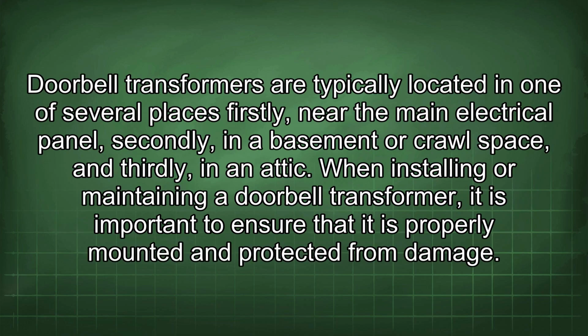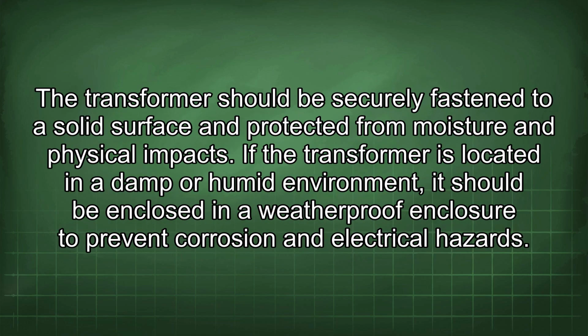Doorbell transformers are typically located in one of several places. Firstly, near the main electrical panel, secondly, in a basement or crawl space, and thirdly, in an attic. When installing or maintaining a doorbell transformer, it is important to ensure that it is properly mounted and protected from damage. The transformer should be securely fastened to a solid surface and protected from moisture and physical impacts. If the transformer is located in a damp or humid environment, it should be enclosed in a weatherproof enclosure to prevent corrosion and electrical hazards.